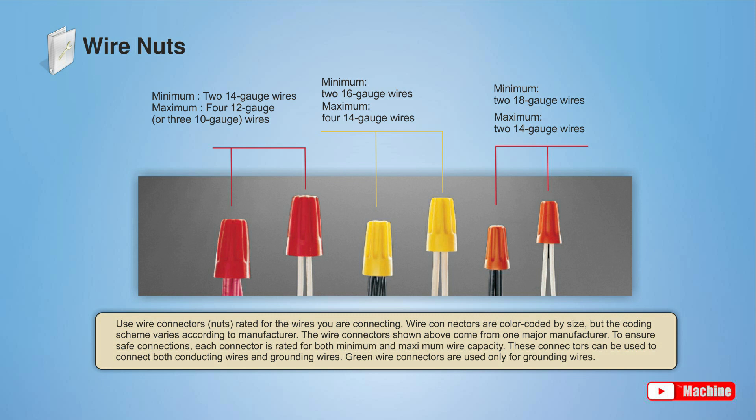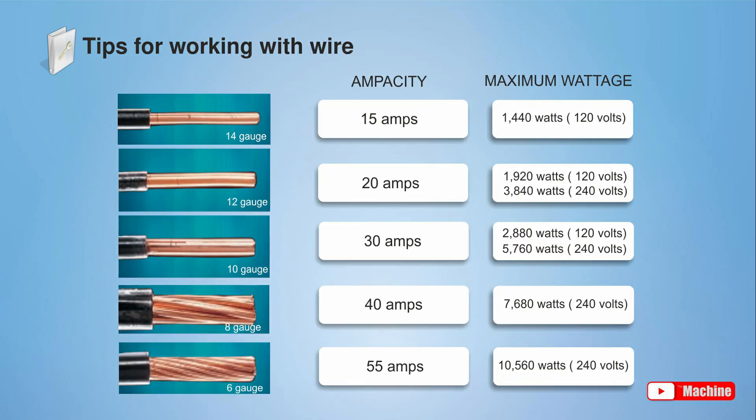Wire connectors are color coded by size, but the coding scheme varies according to manufacturer. The wire connectors shown here come from one major manufacturer. To ensure safe connections, each connector is rated for both minimum and maximum wire capacity. Wire ampacity is a measurement of how much current a wire can carry safely. Ampacity varies by the size of the wire. When installing a new circuit, choose wire with an ampacity rating matching the circuit size.